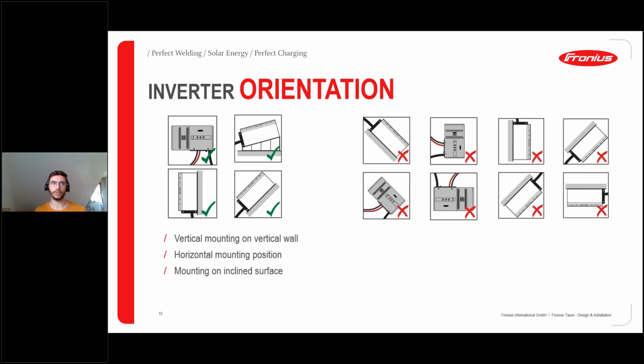For orientation, we can install it vertically up to horizontally without problems. However, we need to make sure it's not tilted sideways, because then the cable glands at the bottom aren't tight enough, and there's a risk that water finds its way into the inverter. So we just need to make sure it's correctly installed and not tilted sideways — that's the only restriction here.